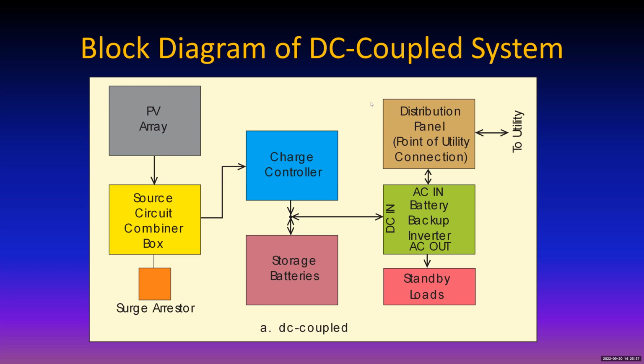So this is the so-called DC coupled system. The only drawback here, there may be more than one, but the main thing is your energy source, the gray box, the PV array, or whatever it might be, is way up there in the left-hand corner, and it has to go through the charge controller, maybe somewhat into the batteries, back out of the batteries, before it gets to the inverter, and oftentimes that inverter will only be 94, 95% efficient before the power actually gets to power up some AC loads. So it's not unusual to lose maybe up to 6% of your available energy in this system.